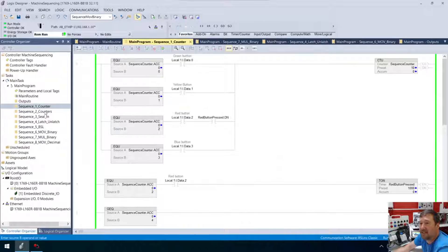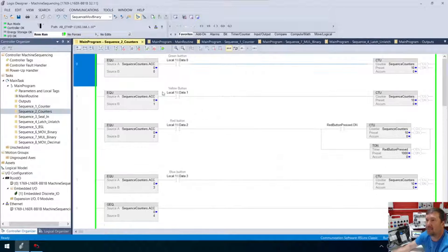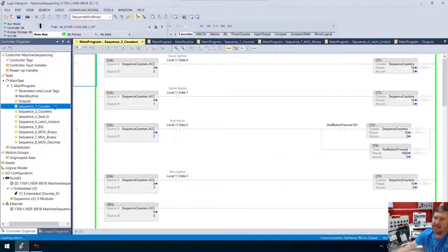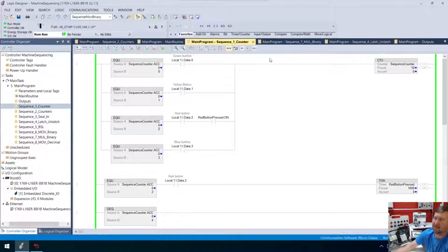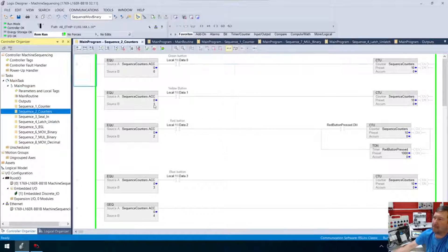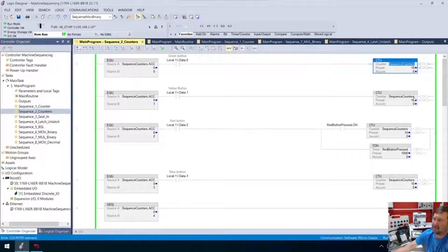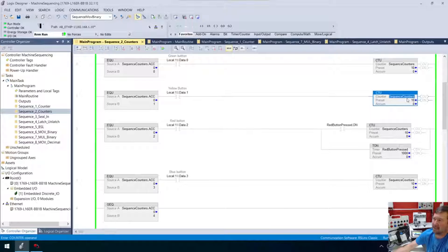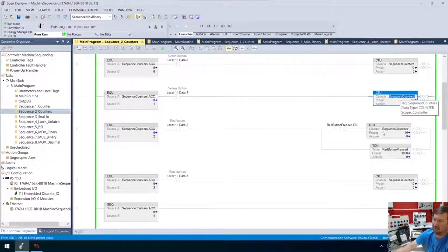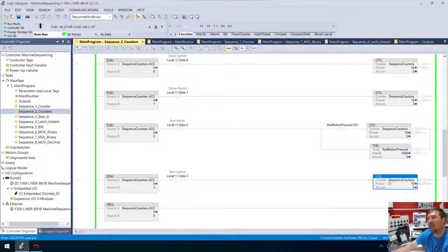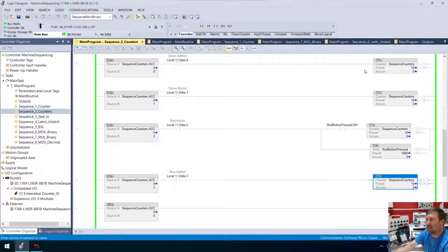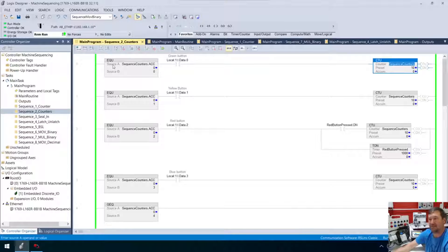We look at our second Studio 5000 example. I've done this. So here are the branches, exactly the same as we have in Connected Components in one counter. But I can break this up. See, this is sequence counter. This is sequence counter. Actually, counters plural, because this is a different one. So I have three count up counters going to the same tag. And I think this makes it easier to read if you're troubleshooting.